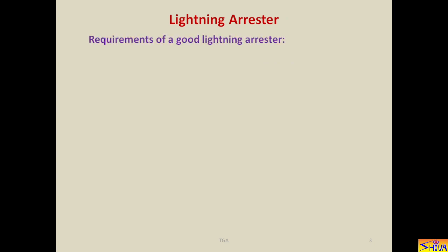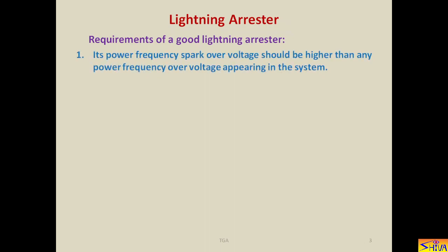Now let us see what the requirements of good lightning arresters are. First, its power frequency spark over voltage should be higher than any power frequency over voltage appearing in the system. So there are two ratings corresponding to the system voltage for the lightning arrestor. One is the rated voltage of the lightning arrestor and second is the rated power frequency spark over voltage. And this power frequency spark over voltage depends on the rating of the lightning arrestor and it is 1.6 times the rating of the lightning arrestor. And the rating of the lightning arrestor is decided from the maximum operating voltage of the system, that is 1.1 times or 1.05 times the system voltage multiplied by the coefficient of earthing. So this is one rating, that is power frequency spark over voltage.